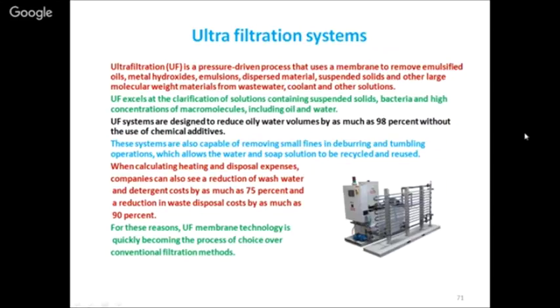Ultra filtration systems are designed to reduce oily water volumes by as much as 98 percent without using chemical additives. They can also remove small fines, allowing water and soap solutions to be recycled and reused. When calculating handling and disposal expenses, companies can see a reduction of wash water and detergent costs by as much as 75 percent, and a reduction in waste disposal costs by as much as 90 percent. Membrane technology is quickly becoming the process of choice over conventional filtration methods.